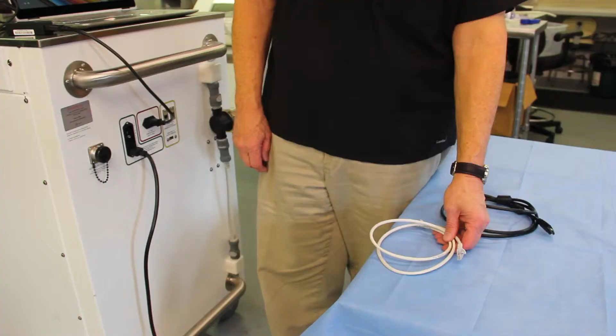The next step is to connect the computer to the CSS, and it is done with an Ethernet cable that is supplied, connected to the computer in the usual fashion using an Ethernet connection. That then connects this computer to the computer inside the base unit, which will be used to drive the action of the CSS. The next step is to connect the output of the computer to the CSS and then display it on the monitor. This is done with an HDMI cable, connected to the CSS and then to the HDMI output of the computer.